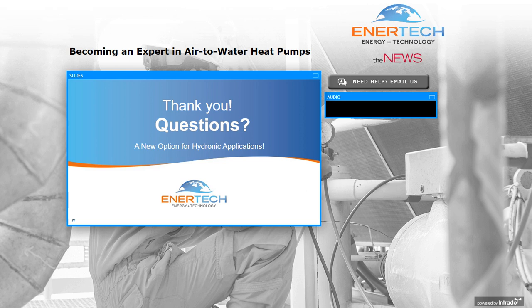Would it be possible to provide multiple output taps for different temperature requirements? Well, that's actually built into it, really. There are two settings, three if you count cooling. There's a water heating setting, so what is being sent over to the TurboMax water heater has a set point. There's a set point for the radiant floor, which is based upon outdoor temperature, so it's the outdoor temperature reset curve. There's also a set point for fan coil heating, and that is fixed at 120 degrees, so we'd want to match it with an Enertech fan coil or air handler. And then the cooling temperature you can set as well for chilled water going through a fan coil. So that's one of the advantages of having this package, is that all of that is built into the indoor module.